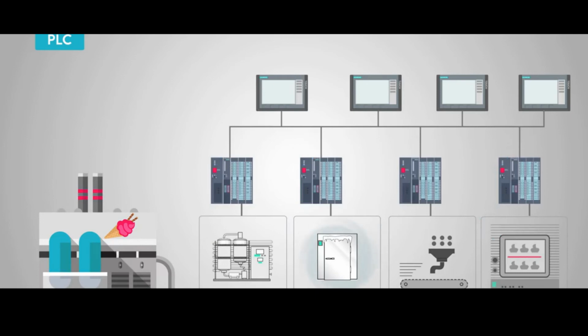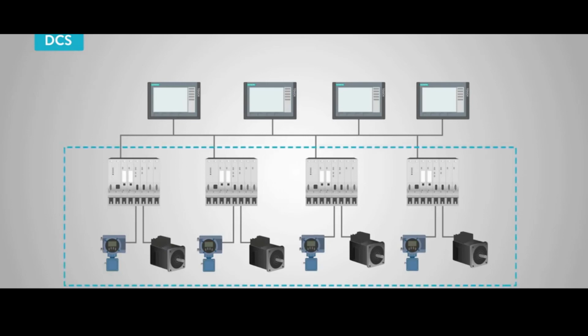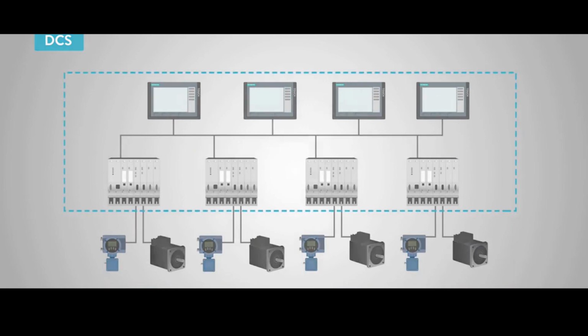You can see that with today's technologies, a wide and robust PLC system could do virtually the same thing that the DCSs can do. An advantage of the DCS is installation costs. This advantage occurs because the autonomous controller can be located close to the process, versus pulling long runs of I/O wire across a plant. Another advantage is the onboard monitoring and control system.